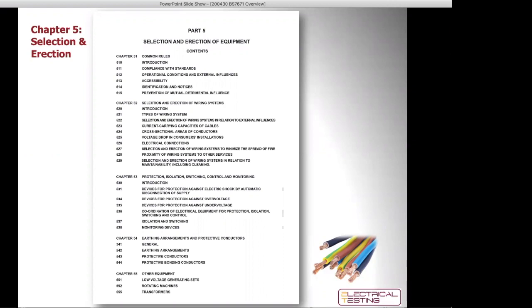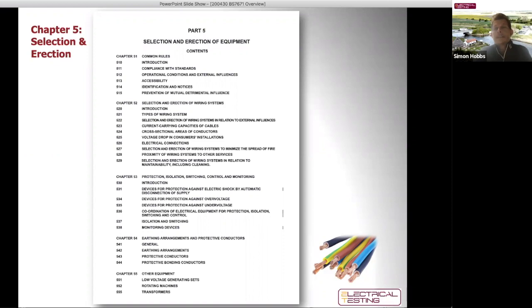Okay, just in passing, the wiring regulations in part 3 have various earthing systems. We've got TNS, where the earth and neutral are separate, and TNC, TNCS, where they're combined. Then there are some specialist earthing systems you find in specialist locations - IT is an independent earthing system, typically found in medical locations and that type of thing. So just some specialist earthing systems that account for a very small percentage of electrical installations.